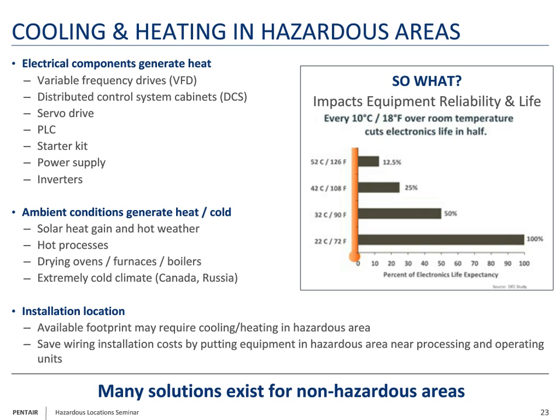Hot processes or processing units create temperature challenges. So if you're by a drying oven, a furnace, or a boiler, they can all create higher ambient temperatures. And then obviously in extremely cold environments like northern Alberta or Russia, you need to warm or keep equipment warm so it doesn't shut down on you. Some reasons why you may have to use cooling equipment in a hazardous area: you might not have the available footprint to take a control panel outside of a hazardous area. If you're on an offshore platform, you have a lot of constraints on where you can put equipment, so you may have to put it into a hazardous area.